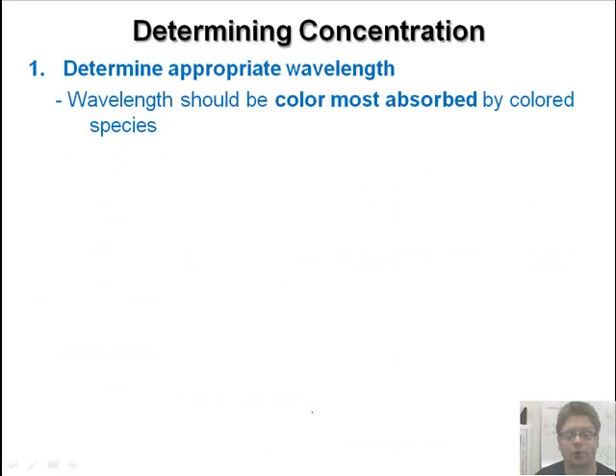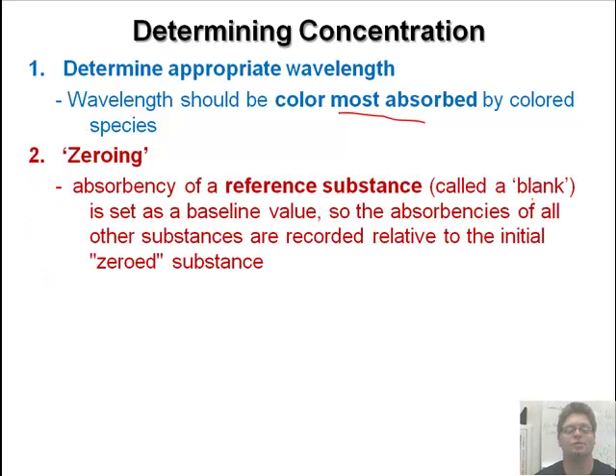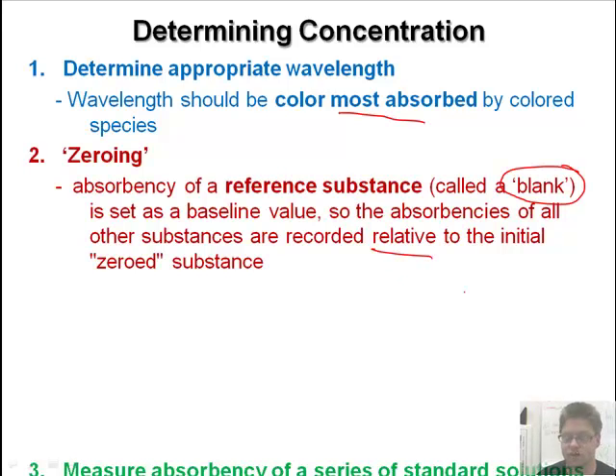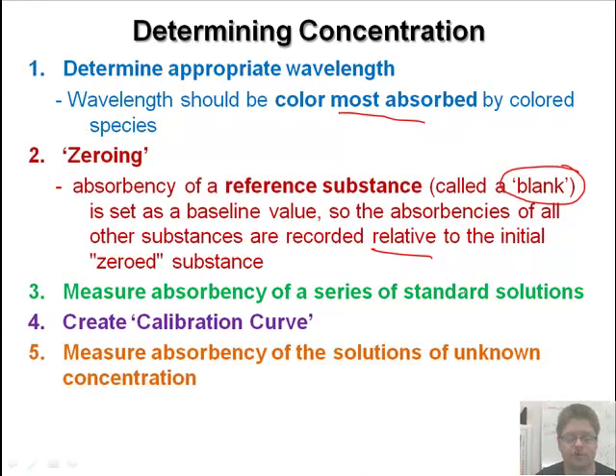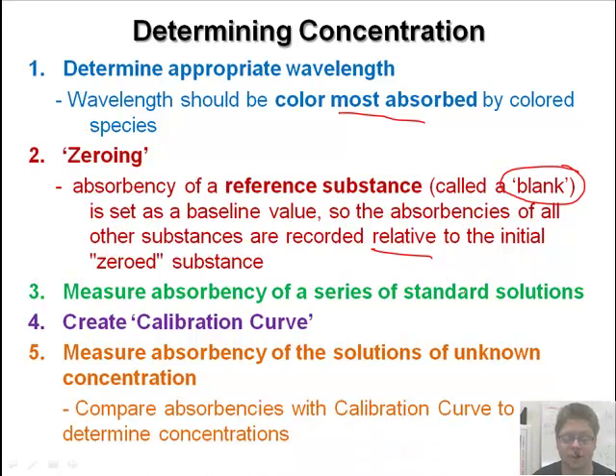Determining concentration: you determine the appropriate wavelength. That's the first step set in the spec 20. Wavelength should be the color most absorbed. You zero the spec 20. The absorbency of a reference substance is called a blank. This is a baseline value, so the absorbance of all other substances are recorded relative to that initial zero substance. Then you do the absorbency of a series of standard solutions. Then you create a calibration curve and measure the absorbency of solutions of unknown concentration. Then you can use your calibration curve to determine the concentrations.